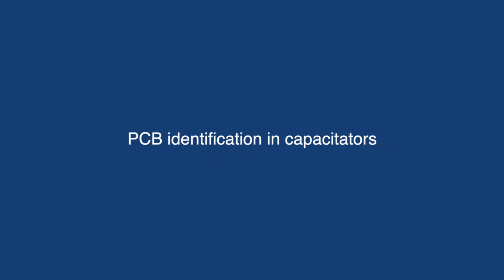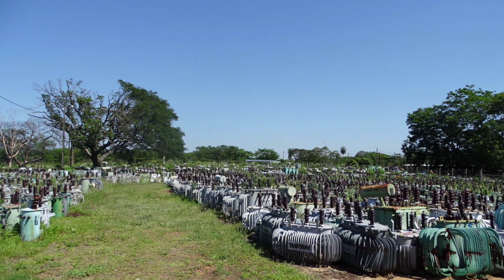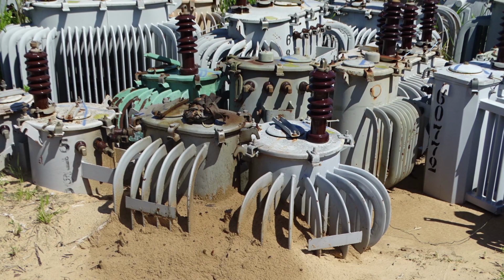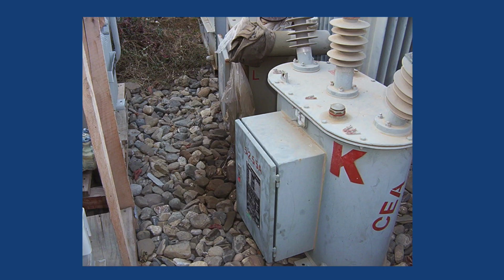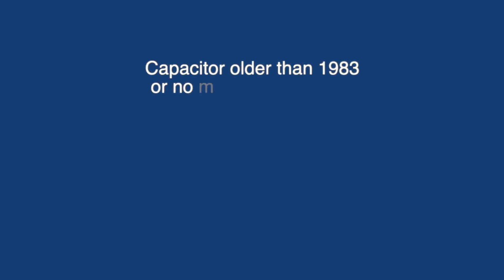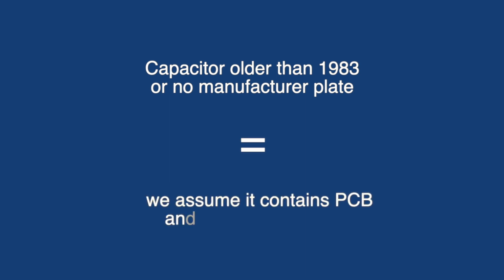Capacitors have no drain valve or other opening, therefore PCB must be identified with the information found on the manufacturer plate of the capacitor. Additional information might be found from lists of manufacturers. In general, literature suggests that if a capacitor was manufactured before 1983, or if it does not have an information plate, we should assume it contains PCB and dispose of it as such.